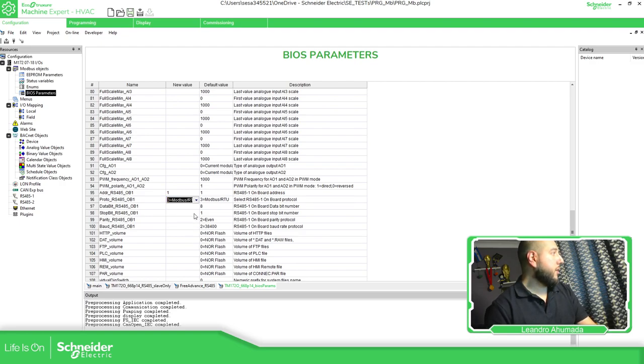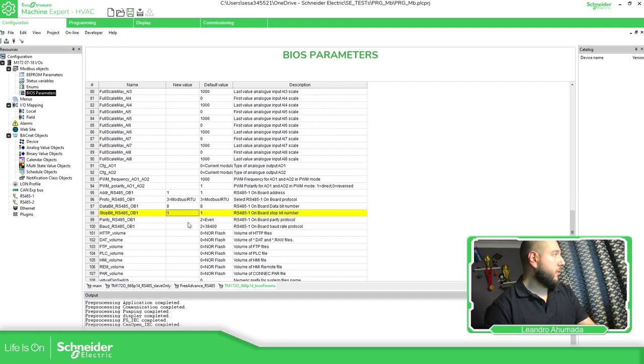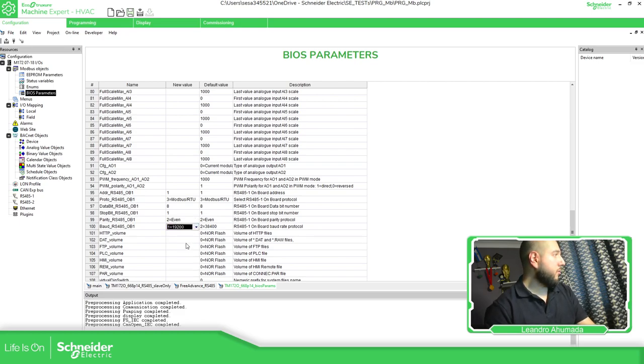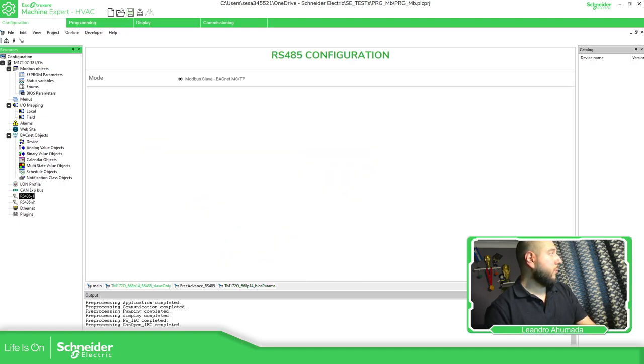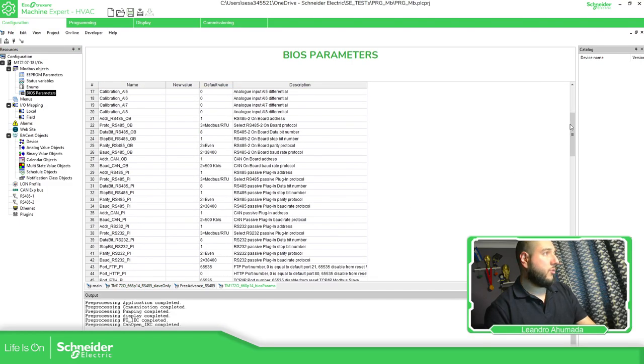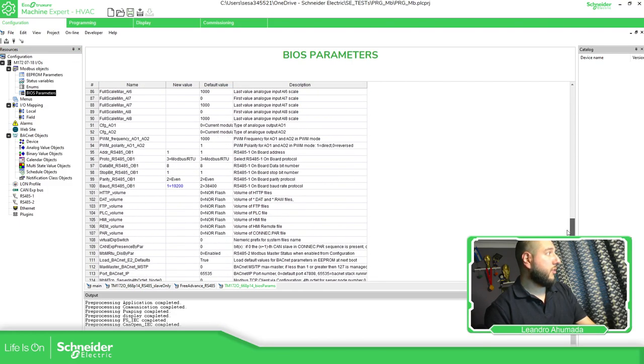And here you have other things to configure the protocol. BACnet, serial, but in this case, Modbus, 8, 1, even, and let's say 19,200. This is going to be the serial one. If you go over here, this is the slave. So we have configured only the slave in this case.